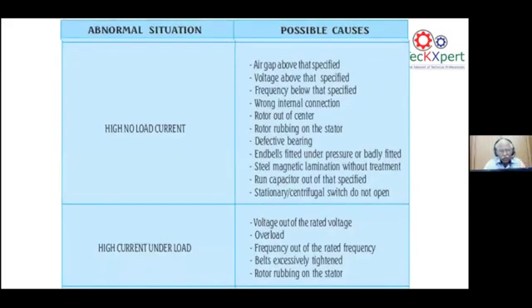Coming to the next cause in the motor, the high no load current. High no load current because of the air gap. Once the rewinding is done, the air gap is not maintained, and definitely it goes for high no load current. Voltage: some of the old, imported motors are rated for 380 volts. We are operating this motor with our non-OLTC type transformer, which means sometimes in the night it goes to 440, 450 also. Then it goes for a higher no load current or a higher motor consumption when the loading is less.